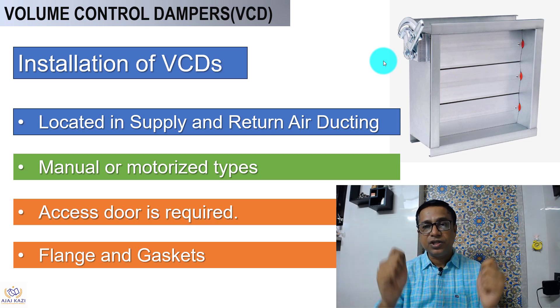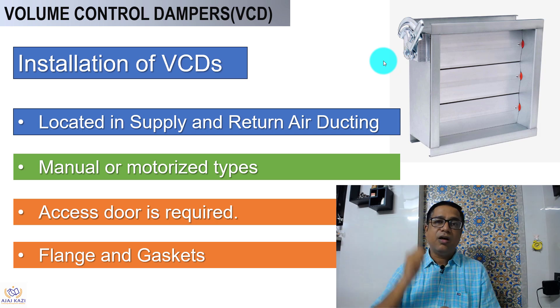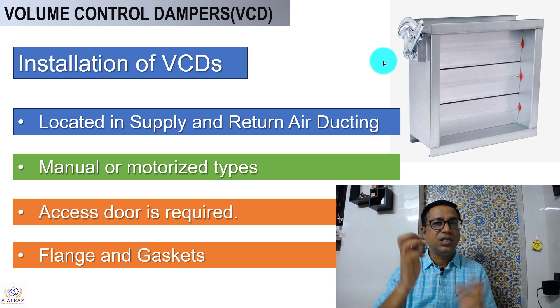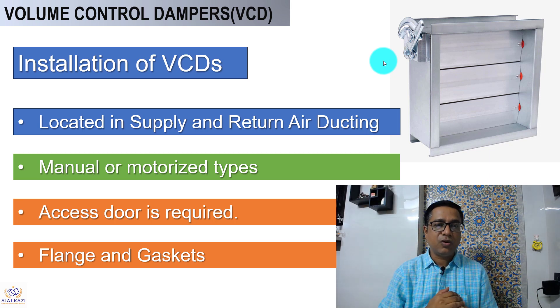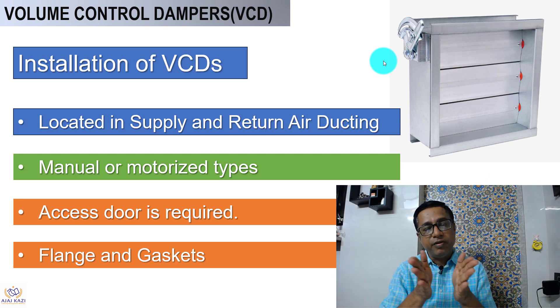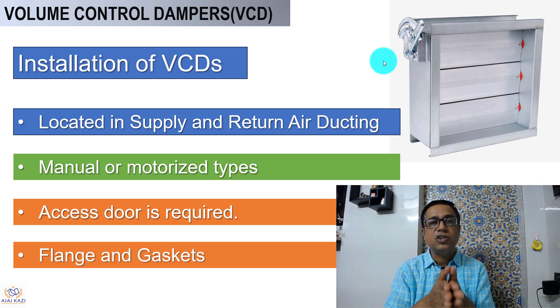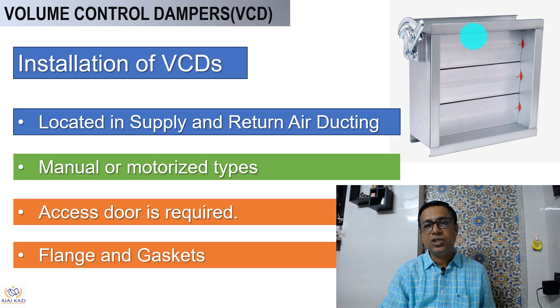For any VCD, because we will need access to open, close, or do air balancing or re-air balancing later on, you need an access panel in the false ceiling — which is very important. Without access, these VCDs will not play any significant role. When connecting VCDs to the duct, there must be flanges and a gasket.